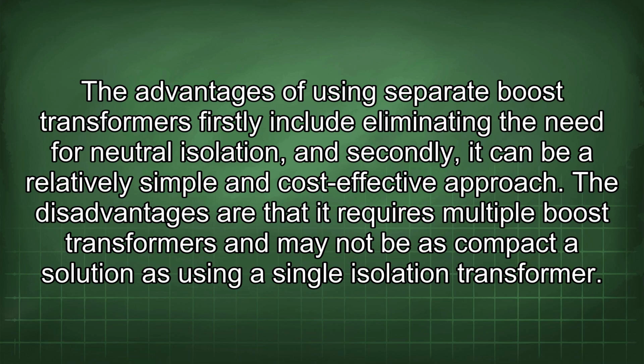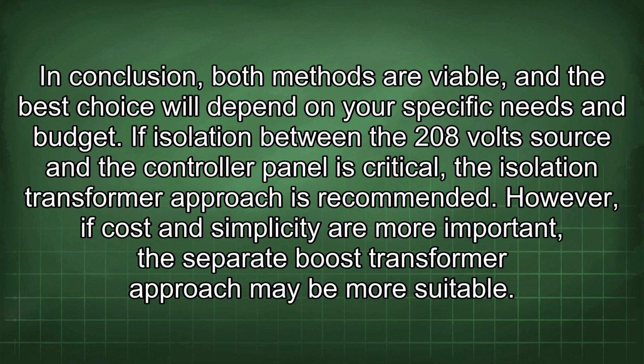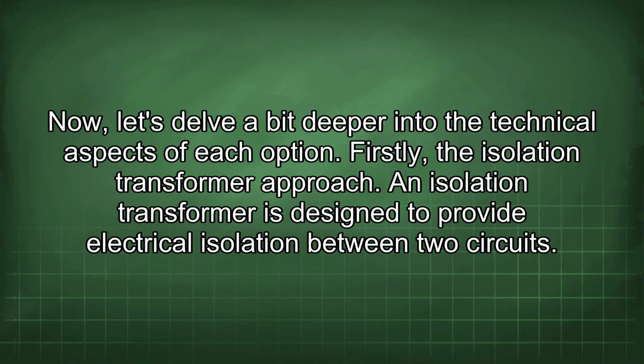The disadvantages are that it requires multiple boost transformers and may not be as compact a solution as using a single isolation transformer. In conclusion, both methods are viable, and the best choice will depend on your specific needs and budget. If isolation between the 208 volt source and the controller panel is critical, the isolation transformer approach is recommended. However, if cost and simplicity are more important, the separate boost transformer approach may be more suitable. Now let's delve a bit deeper into the technical aspects of each option.